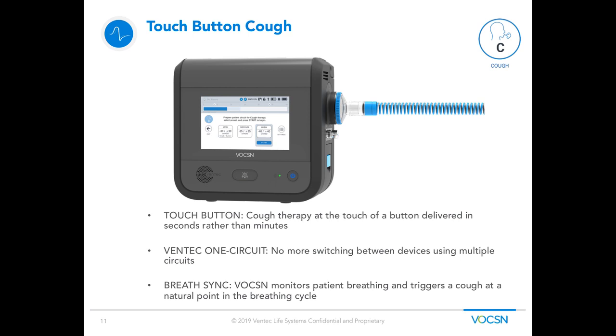However, today with cough assist, you have your ventilator, and cough assist is a separate device with a separate circuit, a separate operating system, separate battery power. And the process is that the patient has to disconnect from the ventilator. That creates a lot of anxiety if you're depending upon that ventilator to breathe for you. You then have to connect to this other device, do your cough assist, which is a big flow of air in, a big flow of air out to bring those secretions up and out.